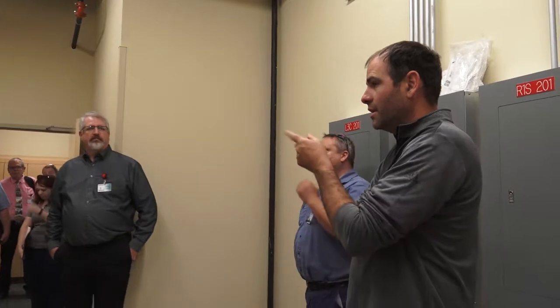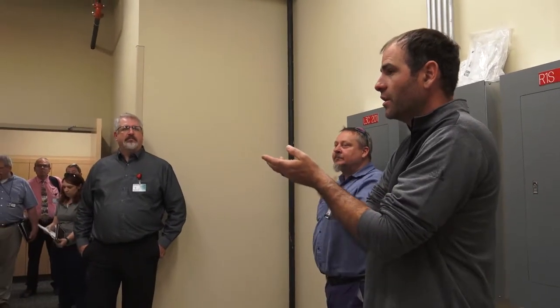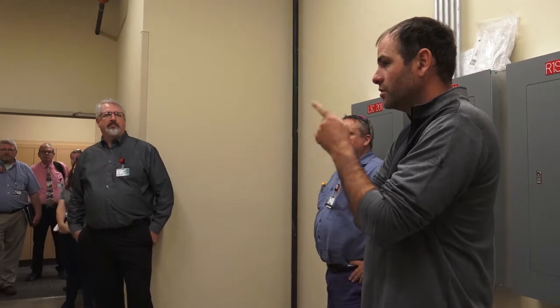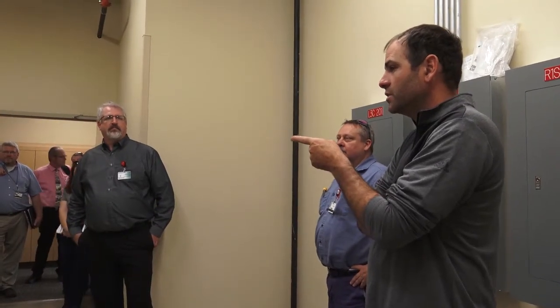So we'll go back that way, and so this lighting control panel is basically just the hallway lights, and there's one relay for that lobby in there. I was telling them, in case it somehow happens to shut off, there is a low voltage override switch out there that you just hit and it'll shut all the lobby lights off out there in the lobby, and it'll turn all of them on. And then it will shut off after business hours, and then it will sweep again to shut off, so they're not on.